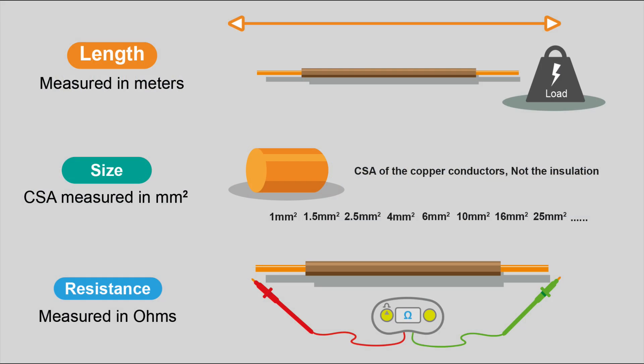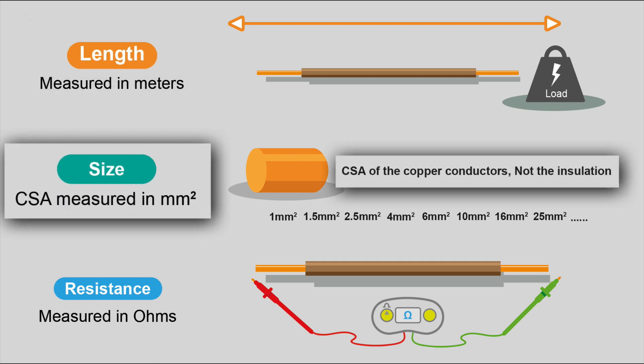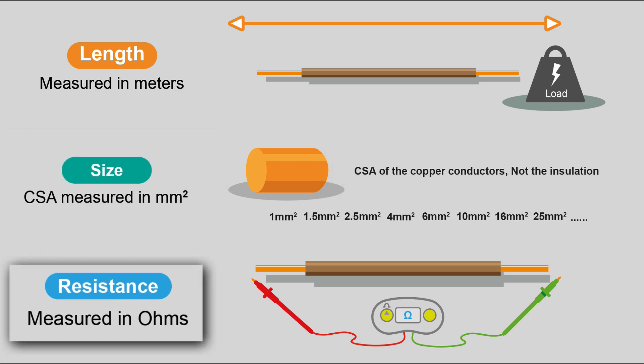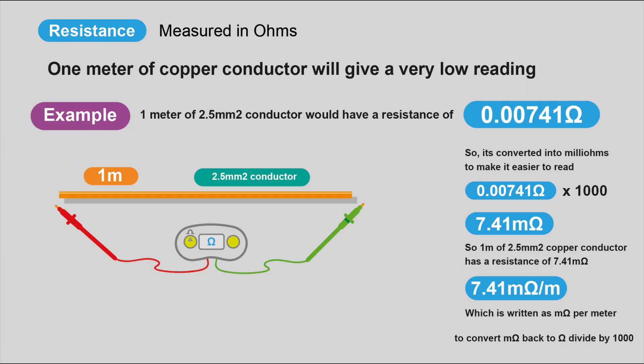So it's really simple to work out the resistance of our cable. We just need to know how long the cable is, what size the cable is in millimeters squared, and what the resistance per meter of the cable is. Resistance is a measure of the opposition to current flow in a cable and it is measured in ohms.